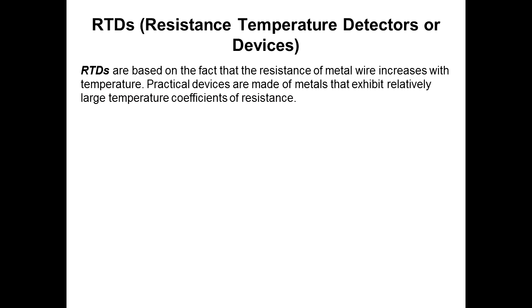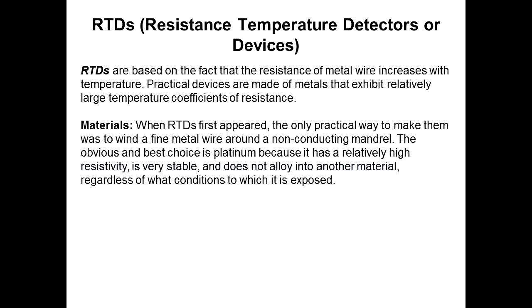RTDs are based on the fact that the resistance of a metal wire increases with temperature. Practical devices are made of metals that exhibit relatively large temperature coefficients of resistance. When RTDs first appeared, the only practical way to make them was to wind a fine metal wire around a non-conducting mandrel. The best choice for RTDs has been platinum because it has a very high resistivity, it's very stable, and does not alloy into another metal regardless of what conditions it's exposed to.